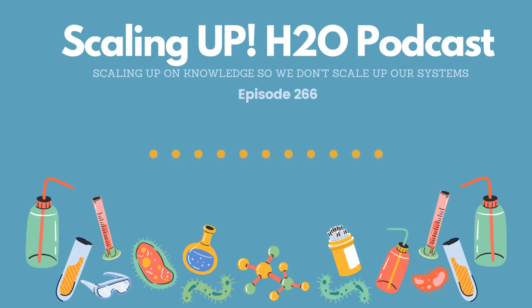Do they care at all about the chiller, or is it all about the cooling tower? They care about chillers that are stagnant—that's what they really care about. They don't care about the model or serial number of the chiller. They don't care if it's shell and tube or a heat exchanger. None of that matters to them. What they do care about is the biocides in use—they want to see an oxidizer. They care that you have some type of corrosion control. They know that Legionella likes iron, so they're aware of that.